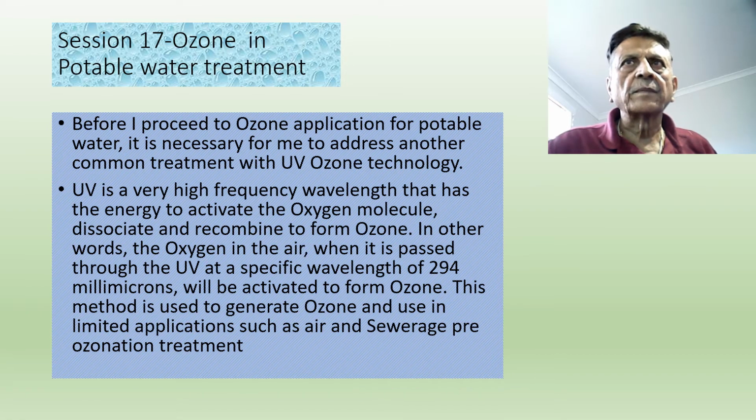Before I proceed to ozone application for potable water, it is necessary for me to address another common treatment with UV ozone technology. We can also produce ozone using UV. UV is a very high frequency wavelength that has sufficient energy to activate the oxygen molecule, dissociate it, and recombine to form ozone. In other words, the oxygen in the air or oxygen itself, when it is passed through the UV at a specific wavelength of 294 millimicrons, will be activated to form ozone.